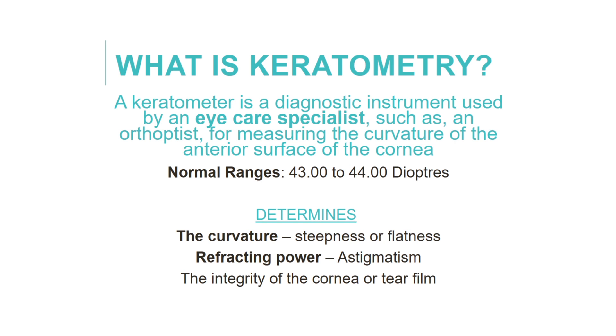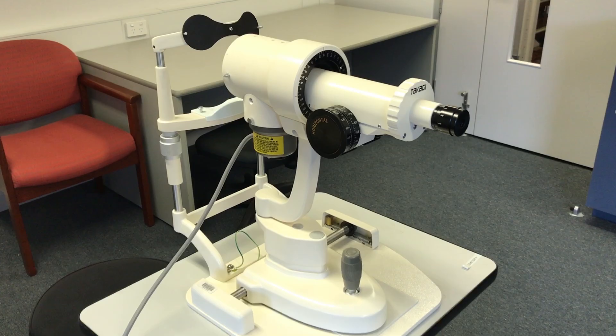Keratometry is the measurement of the anterior corneal curvature. This also determines the power of the cornea. Differences in power across the cornea in both the horizontal and vertical meridians can result in astigmatism. A keratometer can also examine the integrity of the cornea or tear film.